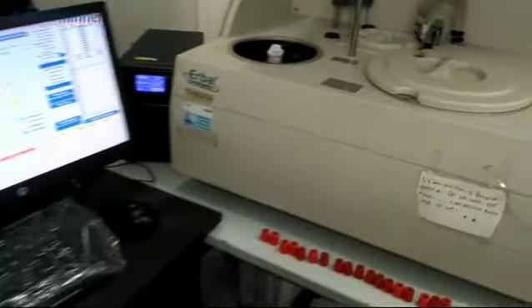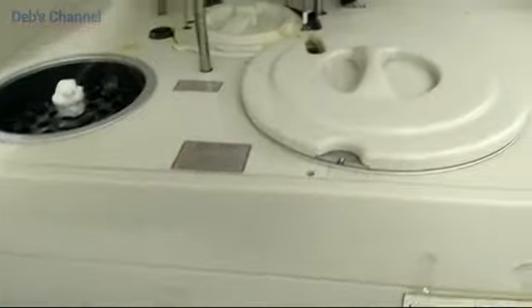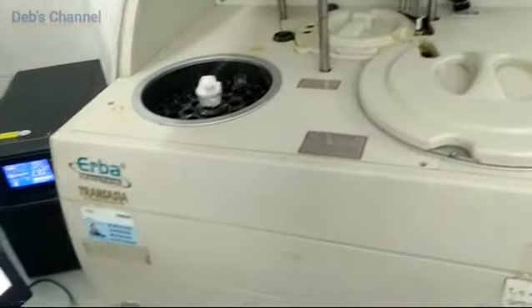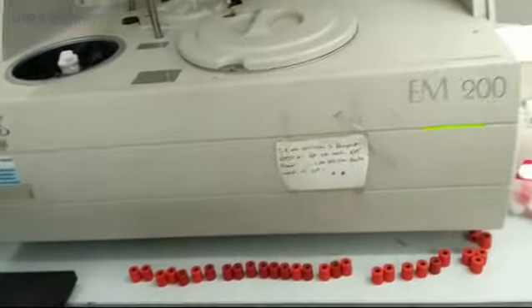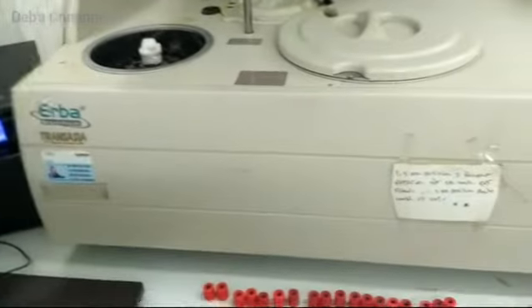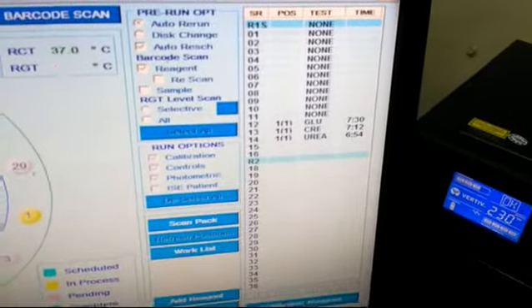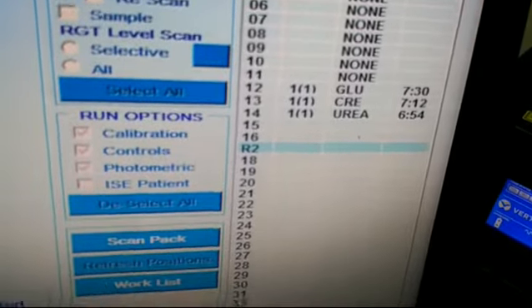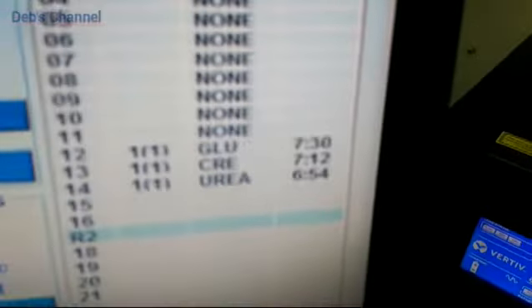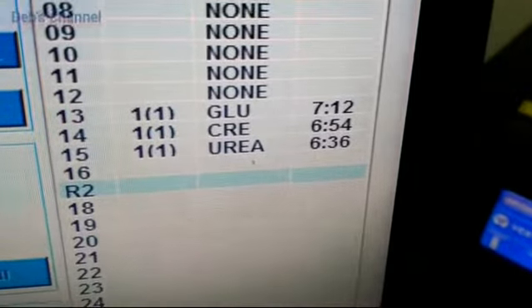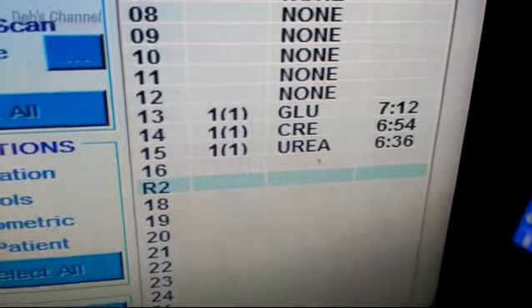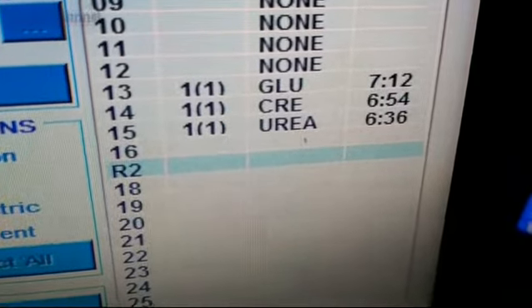Okay, let's go. This is the time for taking the reagent 2. Look at the machine. Whenever the test is going on, the lid will be closed. Now I am demonstrating by opening the lid, but the rule is the lid will be closed to avoid finger prick by the probe. You can easily see the time to complete the test, like 7 minutes and 12 seconds is required to complete the entire test.